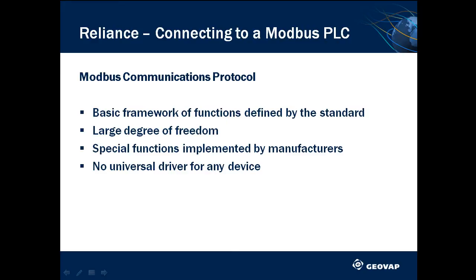The Modbus protocol standard defines the basic framework of functions. However, because the definition is not strict, it offers manufacturers a large degree of freedom to create their own special functions. On one hand, this is fine, but on the other hand, it means that there is no single universal driver for reading data from any Modbus device.